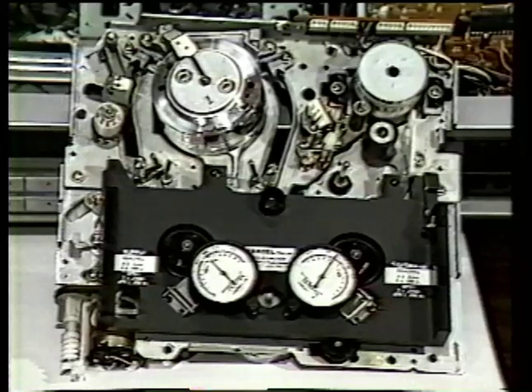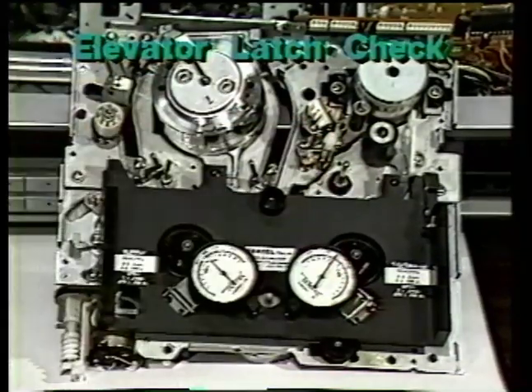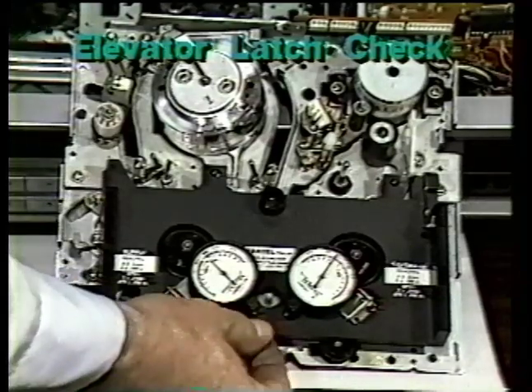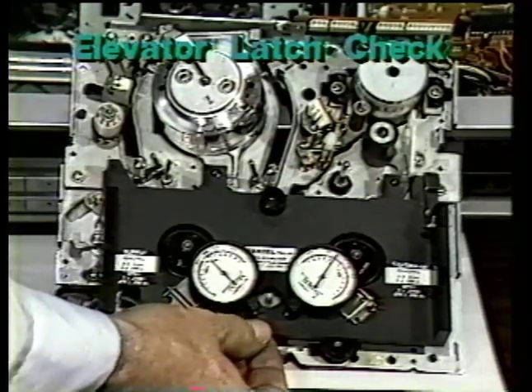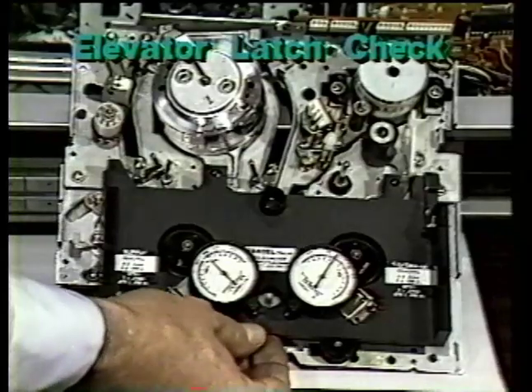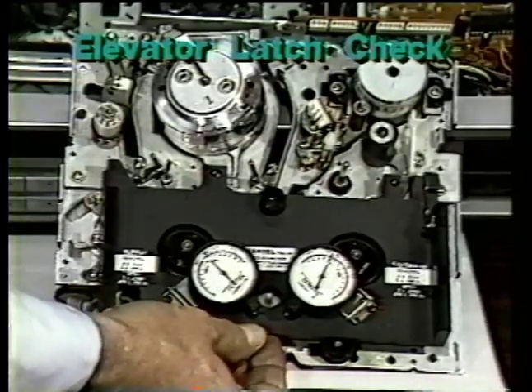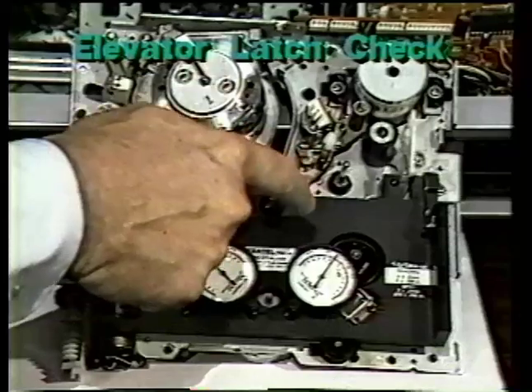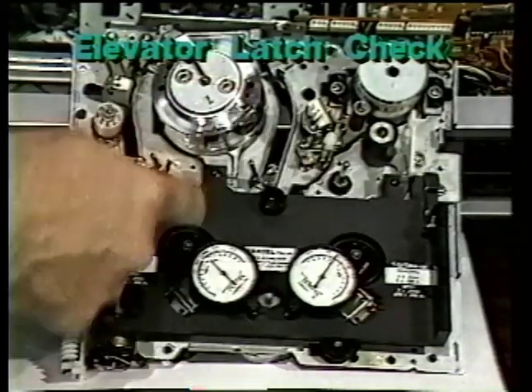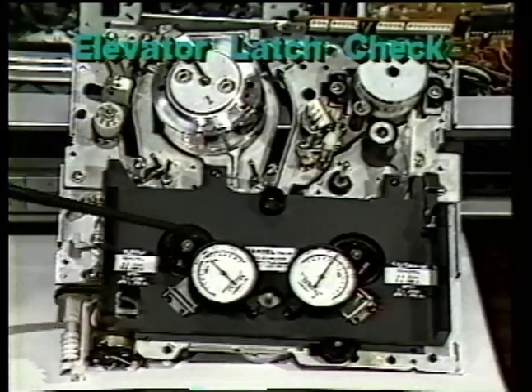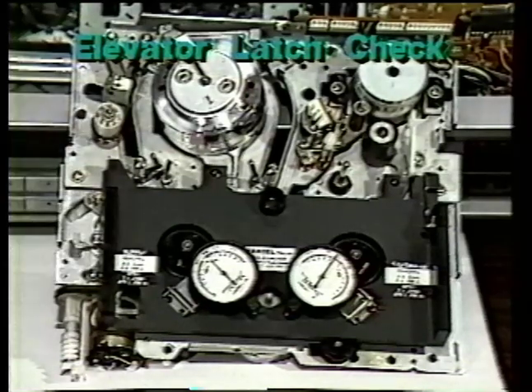So we mentioned the reference plane is a 6-function reference plane. The first thing that we would do is an elevator latch check. If the elevator that carries the cassette into the machine was hanging up or binding, then when we push on the top of the elevator assembly, the indicators would move much like you're seeing here. So as long as this is in fact sitting down flat on these 4 locating pins, then we are reading spindle height above that reference plane. That's 2 of the measurements.